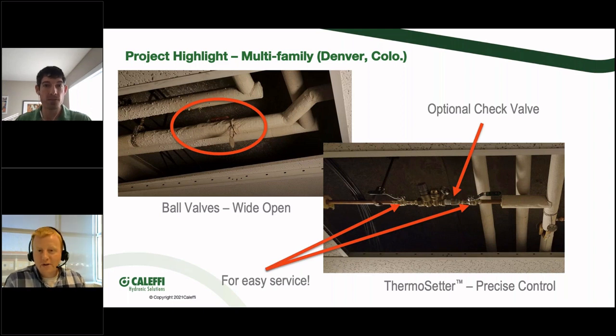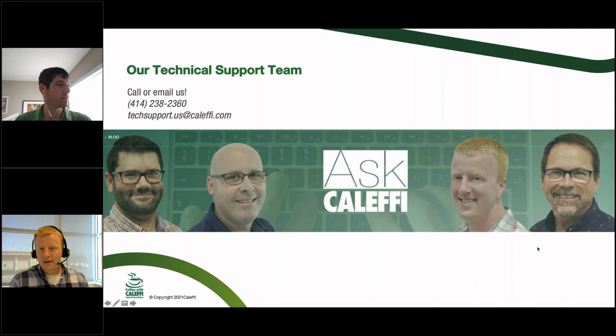No, I think we had a lot of great questions in this webinar, Max. I was keeping an eye on them in the background. A lot of it was about pump applications and settings on your circulators, which I think, again, going back to your pump rep or your pump manufacturer would be a great idea, as far as whether you're doing constant differential or any type of auto mode, and even some of your delta T modes. Because you look at a pressure dependent type balancing valve and you put that in conjunction with a delta T mode on a circulator, you've got a circulator that's varying all over the place, and now all of a sudden you've got a fixed orifice balancing valve that's not moving, and you took all that time to balance it when in all reality the circulator's doing whatever it wants.